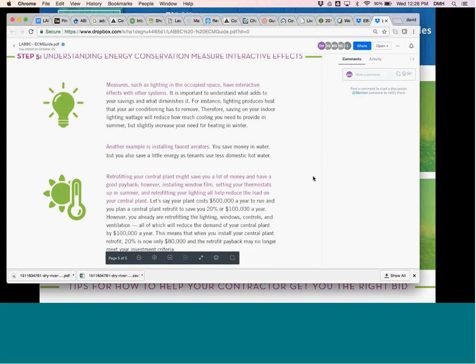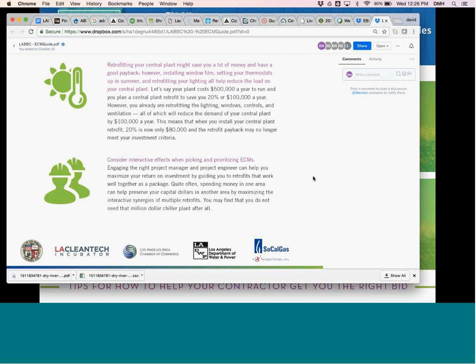Now, a lot of people will say, 'We've got this huge central plant consuming a lot of energy, so we need to save energy there.' But if you jump right in and work on the central plant because it's a big-ticket item, you might lose money or overestimate your savings. Because if you're also doing a lighting retrofit, some window film, and tuning up thermostats, your air conditioning cost is going to go down anyway. So if you then retrofit your central plant, your payback will be longer, since it's now using less energy and you had a fixed retrofit cost to recover.